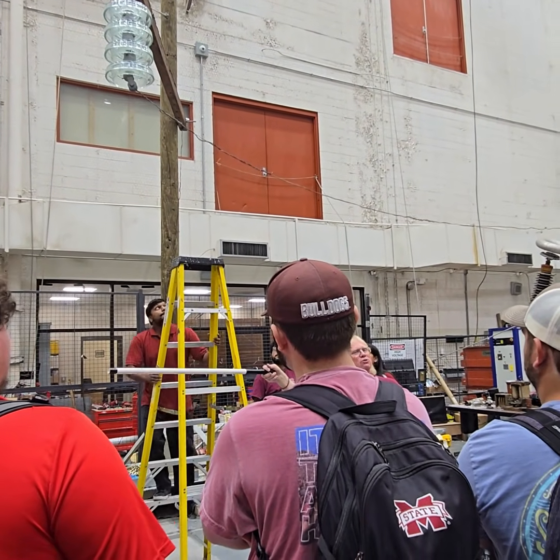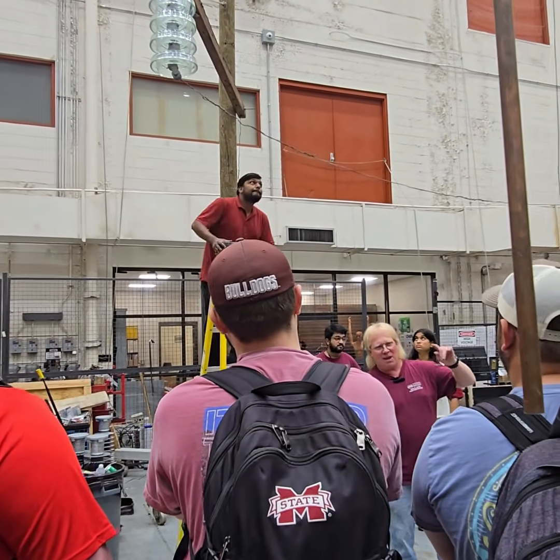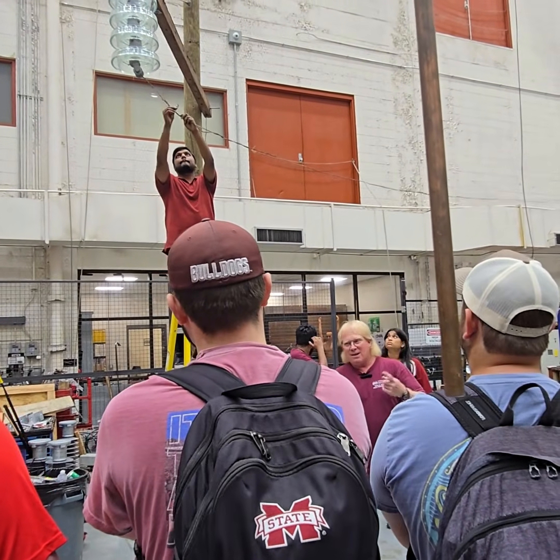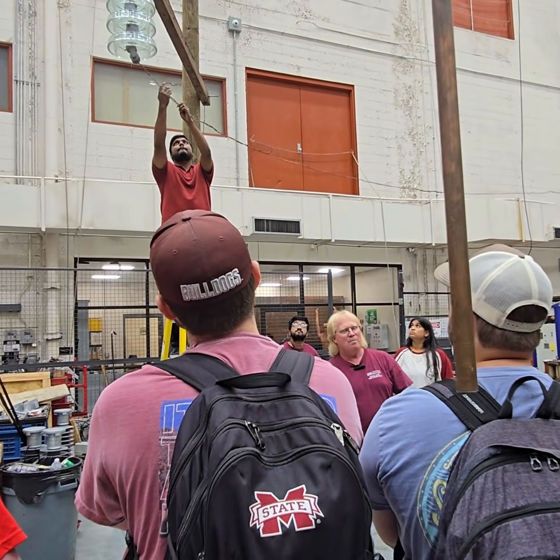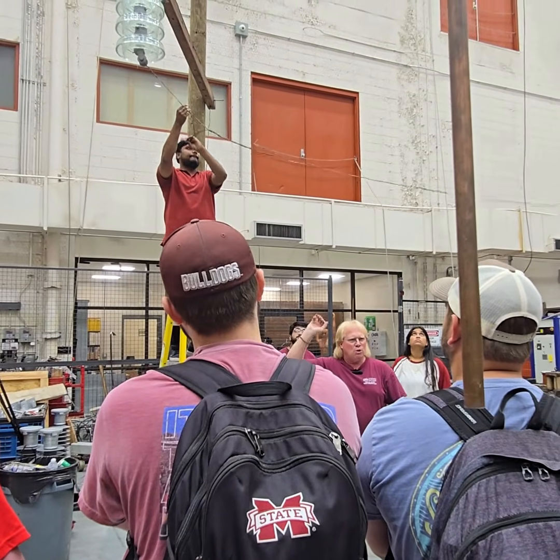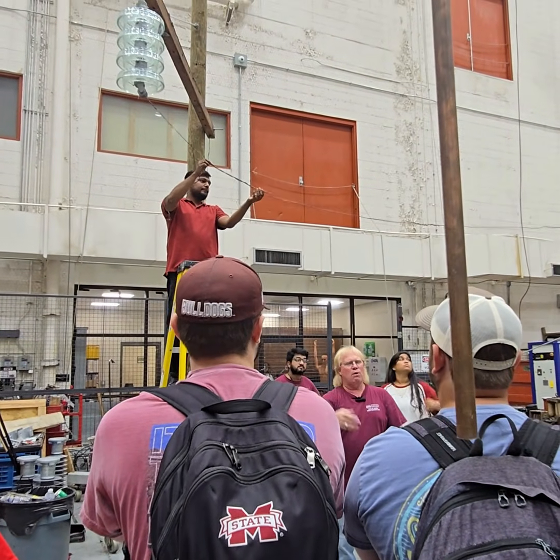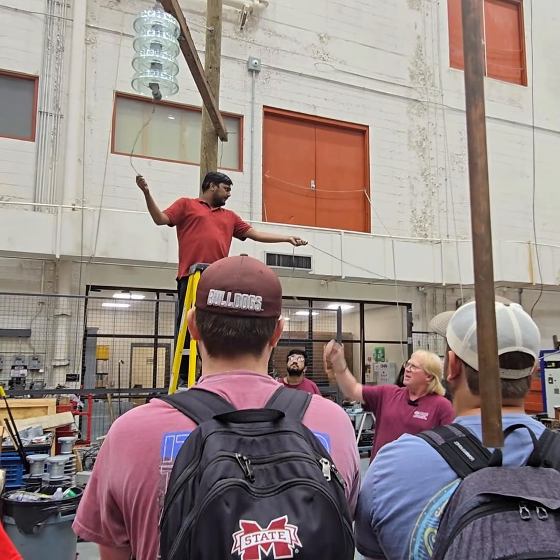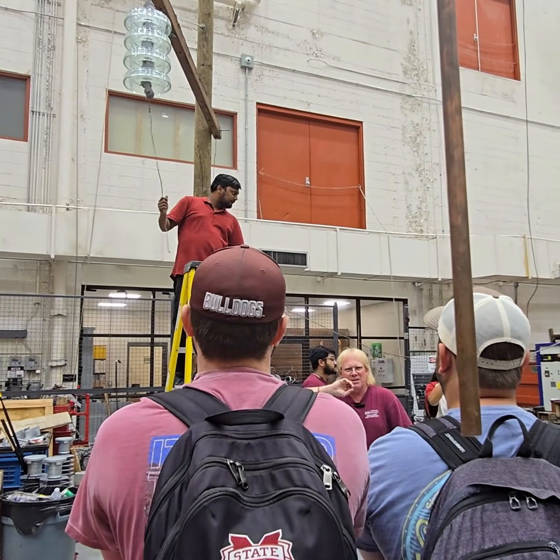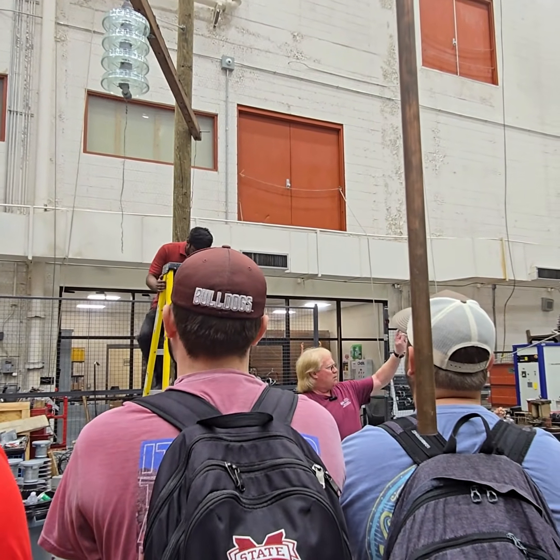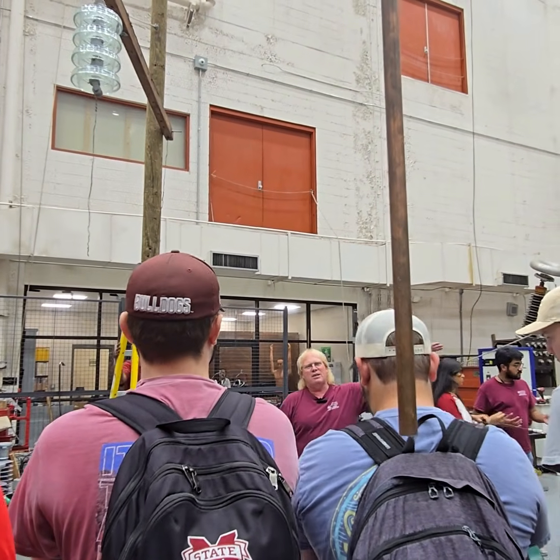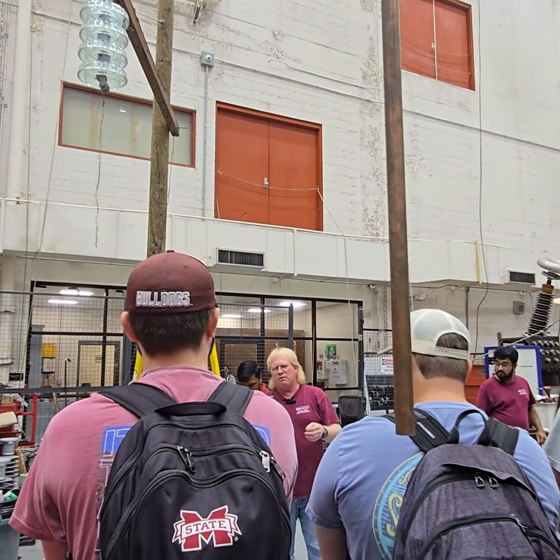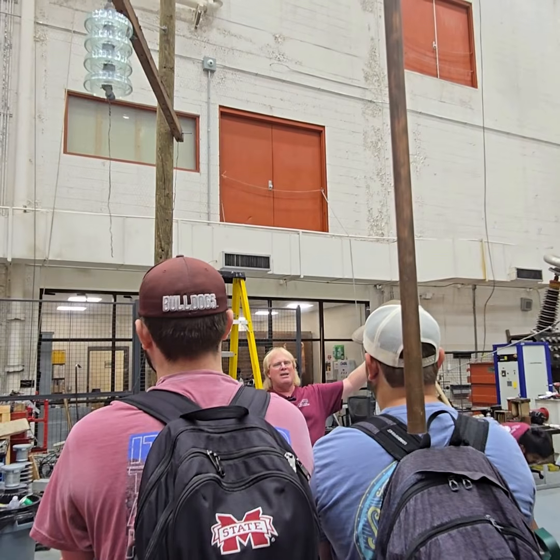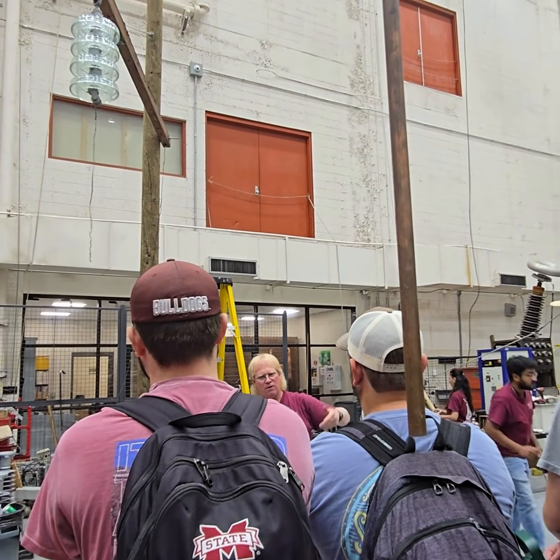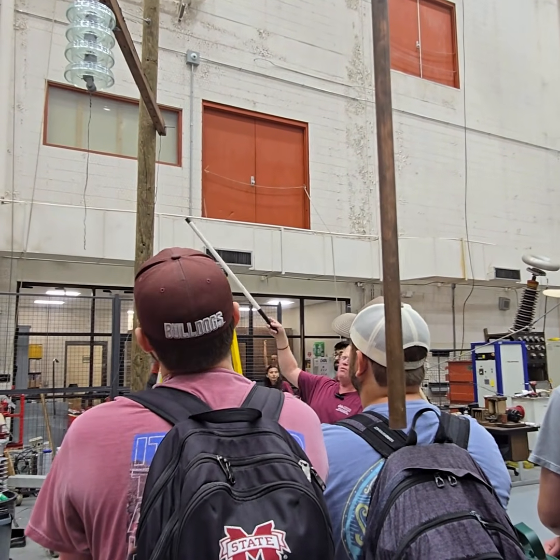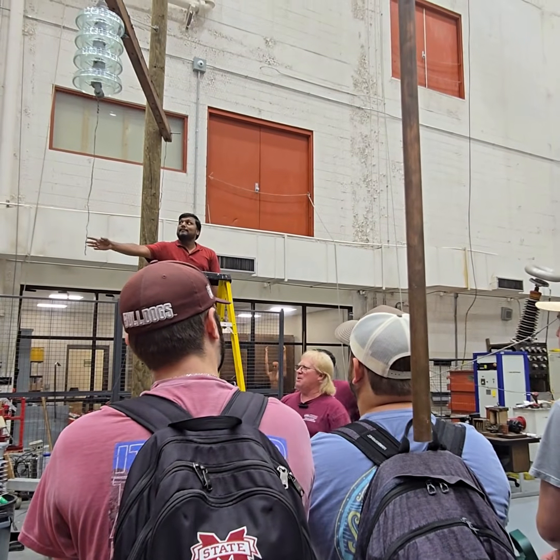But like he said, nitrogen, 79% of the atmosphere you're breathing is nitrogen. Nitrogen in an electric field glows purple. This is what's known as visual corona. We're going to go over corona in the class. It comes from partial discharge. Excitation of the electrons, they eject off, giving you the color. If you go to West Point and see the 500 kV line coming out of the city, on an early morning, if it's very foggy, you'll see those power lines glowing purple from the corona coming off of them. So you'll get to see a flashover, you'll get to see corona here. It's pretty neat.